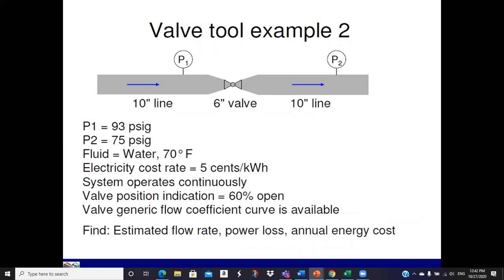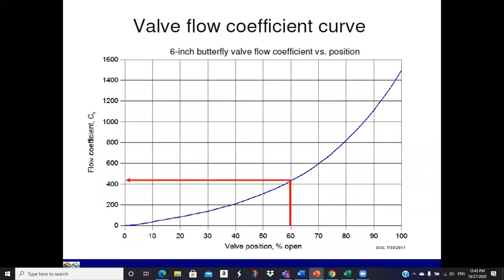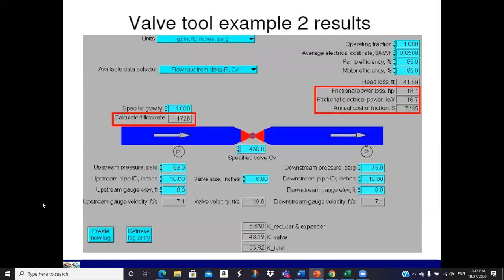Well, this is what happens. You go out in the field and you find a valve and you go, this is 60%, 40% shut, 60% open. So bingo, you go find yourself a curve for the valve. You go in at 60% and you read up and over. And what is that for? There's 500, I don't know, 430, 440.